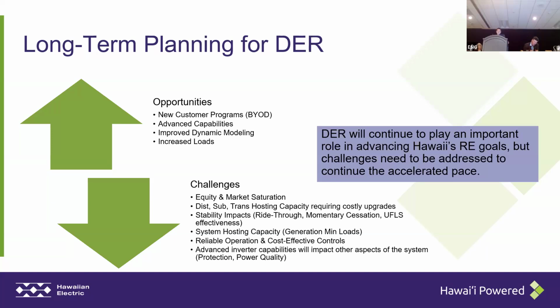On distribution, we're seeing hosting capacity upgrades being required not just on the distribution side, but now going up to the subtransmission. On some circuits we're nearing the point where putting anything DER utility-scale on things connected to certain subtransmission is almost not allowable. There's going to be stability impacts—DERs have ride-through impacts, momentary cessation, and they decrease our UFLS effectiveness. Also, system hosting capacity on some of our smaller islands—we have situations where the generators are running at minimum loads, so we can't take any more on those islands.